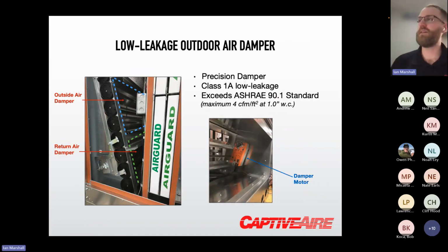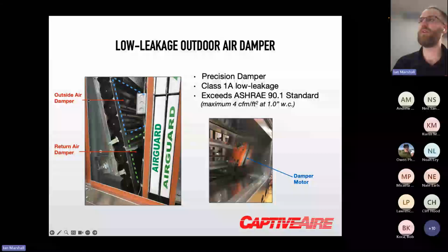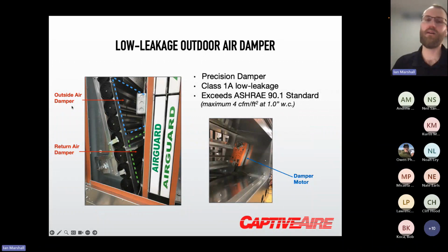Our damper is a mixed damper, so it's an outdoor air return air damper. It's a single damper assembly for the outdoor air and return air. So the bottom portion is the return, if we have a return, and the top portion is the outside air. This is the standard damper assembly for all units, whether they have return or not. But it's a really high-end damper assembly manufactured by Ingenia out of Italy, and there's no play in the gears. It exceeds the ASHRAE Class 1A low leakage standards, and we utilize a Belimo actuator as well.